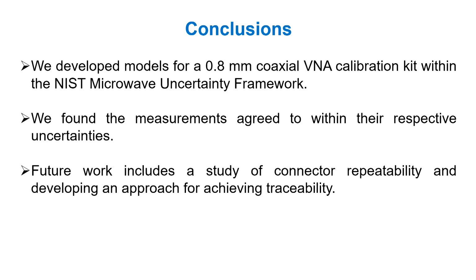So you're talking about how can you tell if one of your calibration devices maybe in your kit isn't working right? Yeah, that's always difficult. One typical thing to do is perform a calibration and then have some verification devices you can look at. And if you try to keep a history of your verification device, and if it looks like it's out of spec, then you have to start looking a little more carefully. Yeah, if it's a lumped element kit like open short load, you can try to measure it with a TRL calibration and see if it's giving what you think it is.